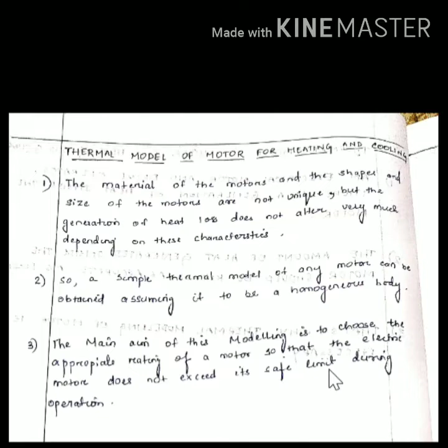With this assumption, the thermal model cannot be said to be a perfect model, but it is suitable for electrical drive engineers to select the motor rating for a given application, ensuring temperature at various body parts does not exceed safe limits. Let's suppose the machine is assumed to be a homogeneous body and the cooling medium has the following parameters. The main aim of this modeling is to choose the appropriate rating of the motor so that the electric motor does not exceed its safe limit during operation. This is the main phenomenon of the thermal model of motor for heating and cooling.